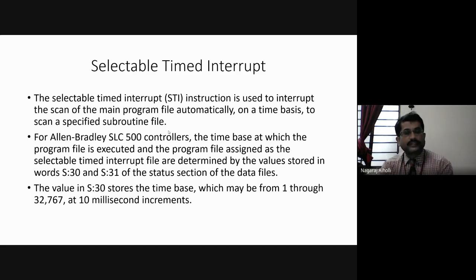And timed interrupt means it is not event based, but it is based on the time. The subroutine, which is meant to provide the service for the requested interrupt, will execute for a particular amount of time. For an Allen Bradley SLC 500 controller, the time base at which the program file is executed and the program file assigned as the selectable timed interrupt file are determined by the value stored in words S:30 and S:31 of the status section of data files.